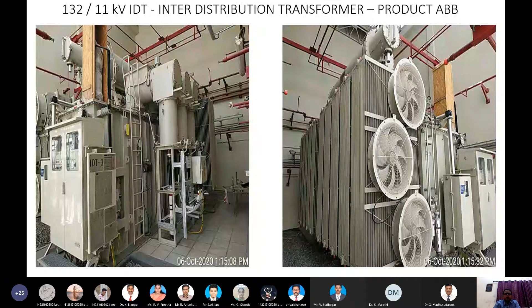The inter-distribution transformer, IDT. The basic principle of the transformer is to step down the voltage from 132 kV to 11 kV, so that it can be transferred at 11 kV for the end user supply. Each substation has a minimum of three IDT transformers. It depends on the specific design approval, whether it is for industrial use or if it's going to be overloaded, so they can expand up to 4 and 5. In the designing stage, they keep extra space, one or two, for IDTs for future expansions. That is how they are designing as of now. Each transformer generates 60 MVA (megavolt-amperes) during the step down process.